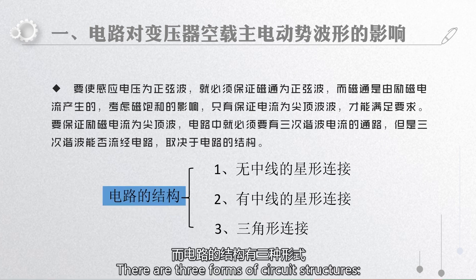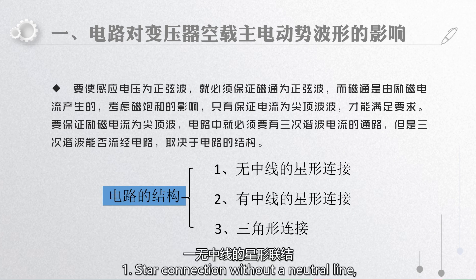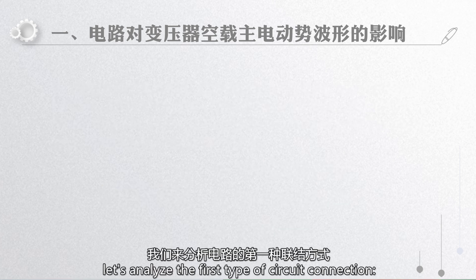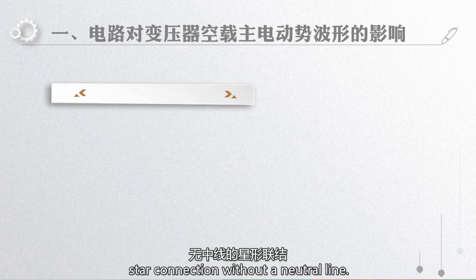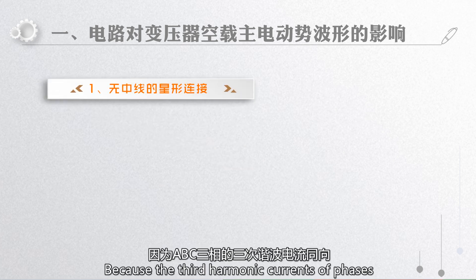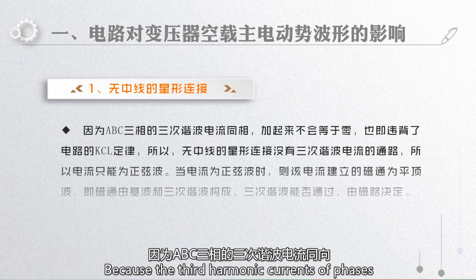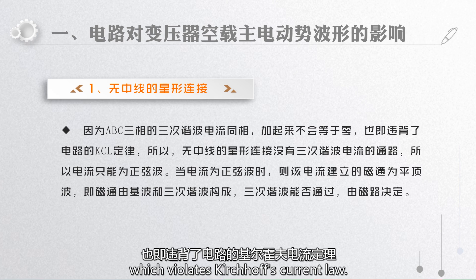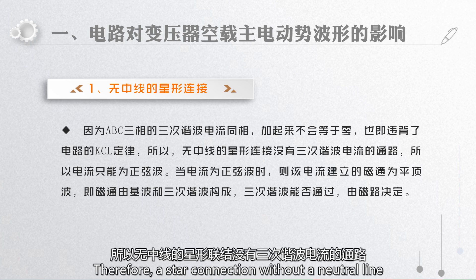There are three forms of circuit structures: 1. Star connection without a neutral line. 2. Star connection with a neutral line. 3. Delta connection. Let's analyze the first type: star connection without a neutral line. Because the third harmonic currents of phases A, B, and C are in the same direction, they do not sum to zero, which violates Kirchhoff's current law. Therefore, a star connection without a neutral line has no path for the third harmonic current.